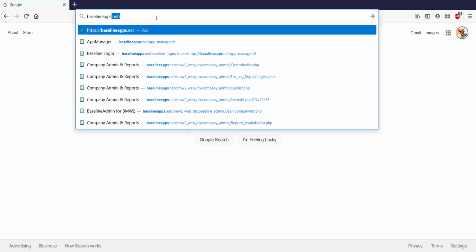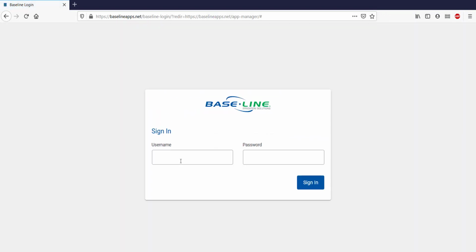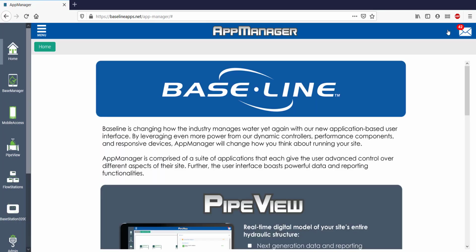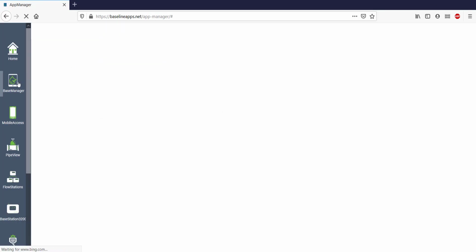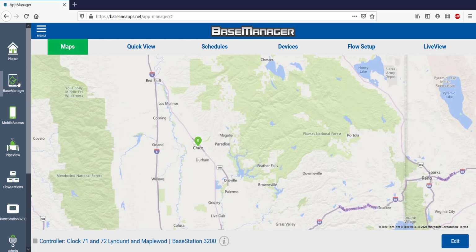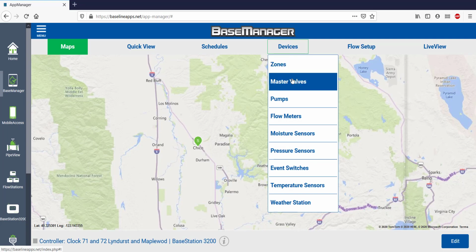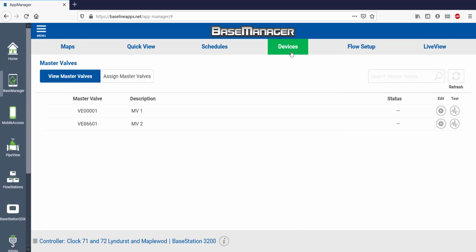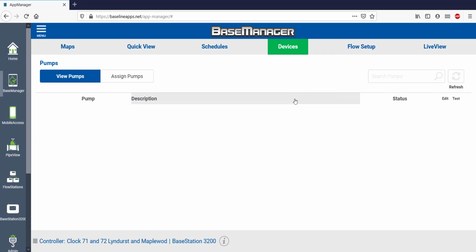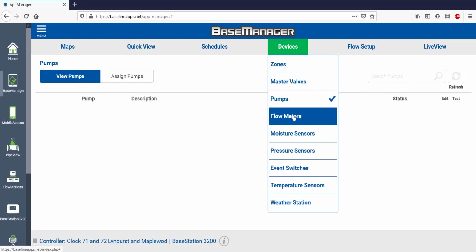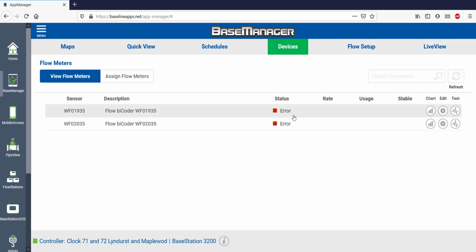Begin by opening a web browser and going to baselineapps.net and then log in with your username and secure password. Look for the Base Manager icon on the left side of the screen. Before we get into flow setup, we'll want to verify that our flow devices are already assigned. Click on the Devices tab and then look for all of your master valves in the assignment list. I don't have any pumps, so this section is empty. There are 2 flow meters on this project, and they both show up in the list as well. This project has slightly more complex hydraulics: 2 master valves, 2 flow sensors, and 1 mainline.